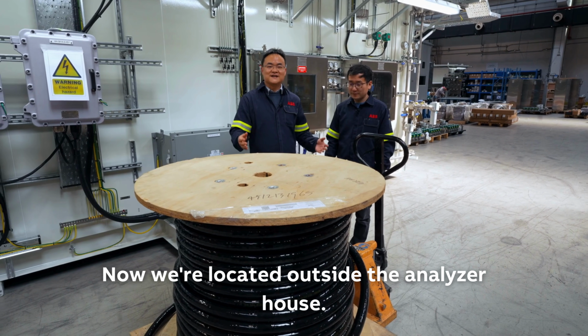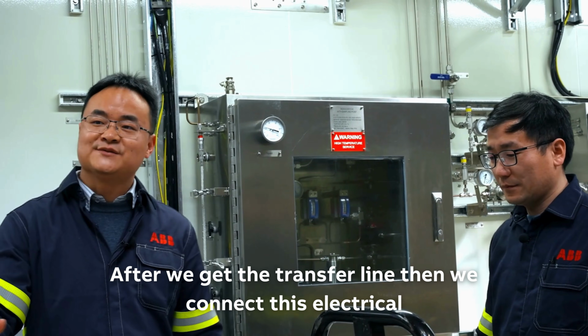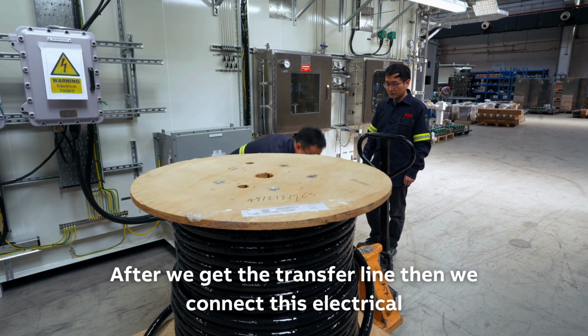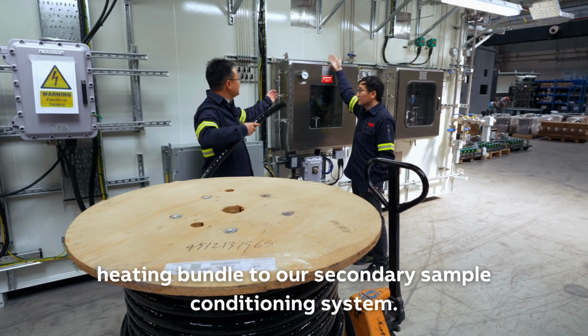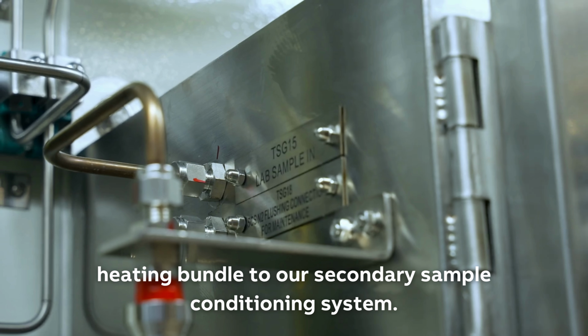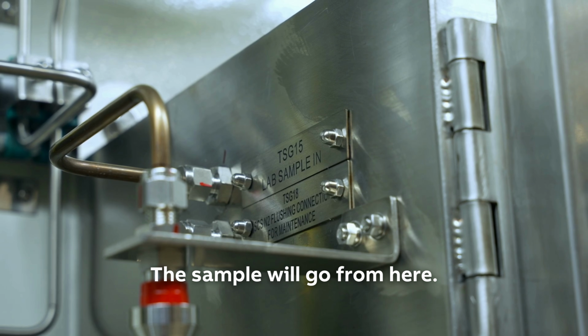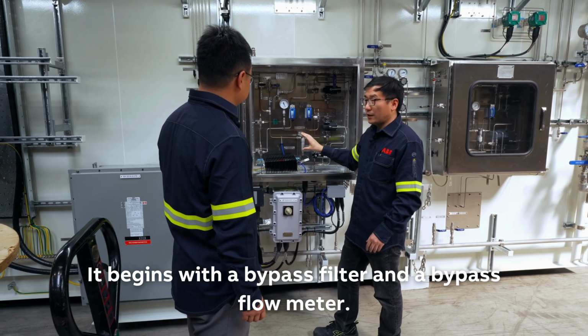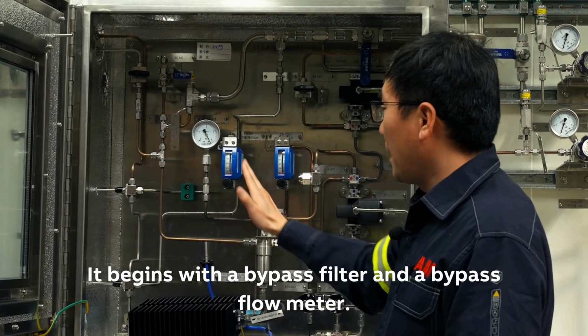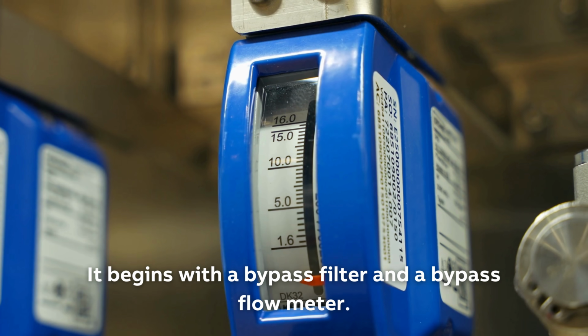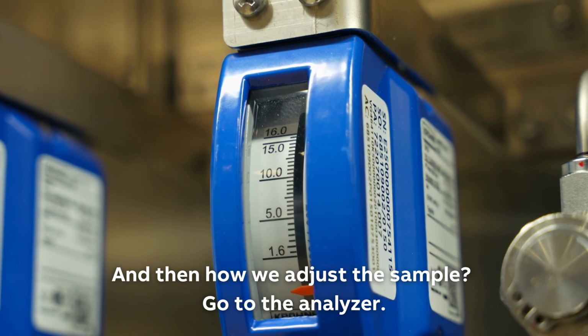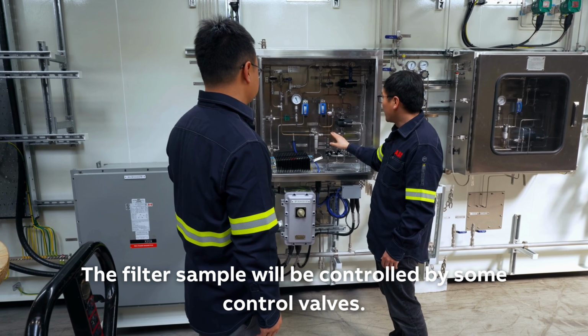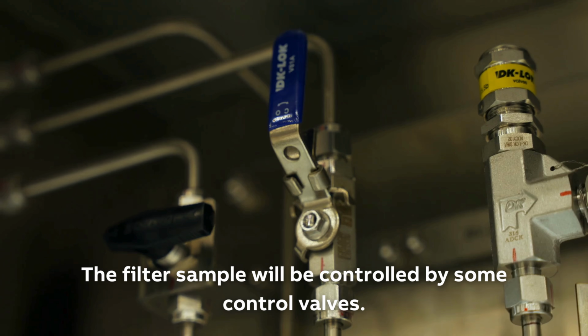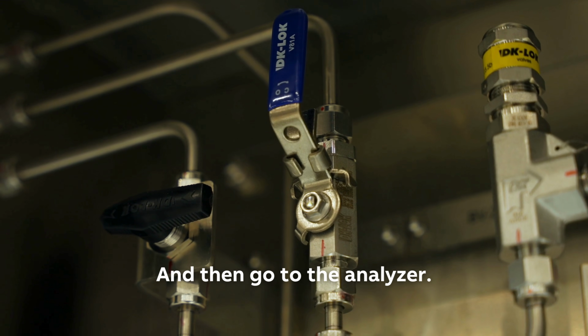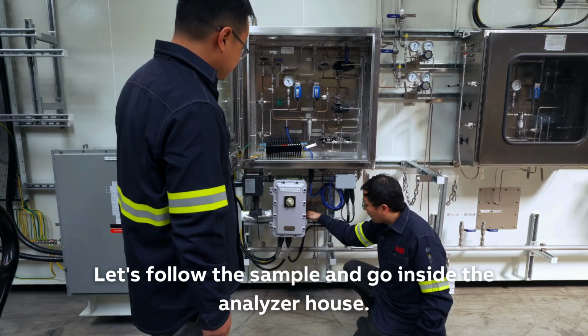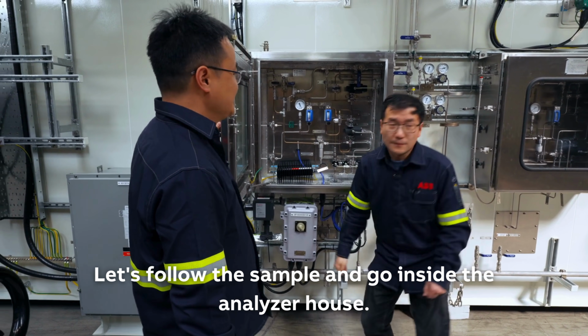Now we're located outside the analyzer house. After we get the transport line, we connect this electrical heating bundle to our secondary sample conditioning system. The sample will go from here. It begins with a bypass filter and a bypass flow meter. And then we adjust the sample to go to the analyzer. The filtered sample will be controlled by some control valves and then go to the analyzer. Let's follow the sample and go inside the analyzer house. All right, let's go.